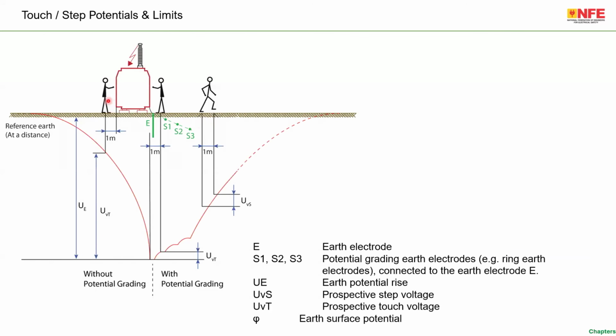The same figure from EN 50522, exactly what we are talking about. As you can see here, there is a transformer, there is a fault. S1, S2, S3 are called potential grading electrodes. Potential grading electrode, for example, a ring earth electrode connected to the earth electrode E. So basically there is a fault. The person who is touching, you can see here UVT is the touch voltage and the example of a step voltage. All these are explained, and the voltage gradient UE is explained in this particular figure.